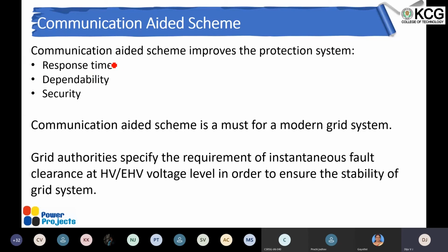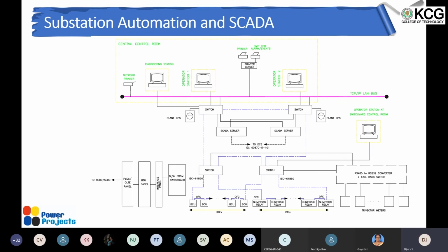So a communication aided scheme is a must for the modern grid system, because the grid authorities always specify the requirement of instantaneous fault clearance at HV and EHV voltage levels in order to ensure the stability of the grid system. So it's not an option, it's a must. The communication scheme should be used for the protection system. Other communication related points with respect to a protection engineer, I'll just explain, not going into the detail. You may know about SCADA, wherein we take the information from all the monitoring devices, the status of breakers, maybe the temperature levels of transformers and other things, motors, everything.